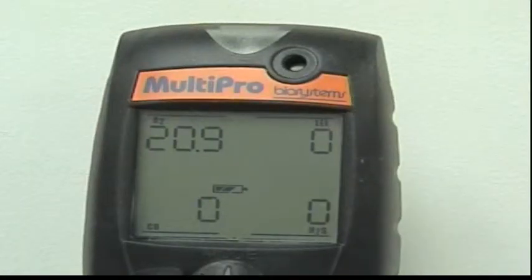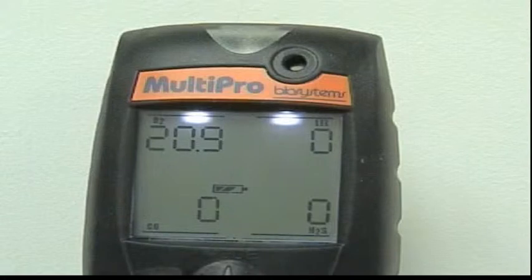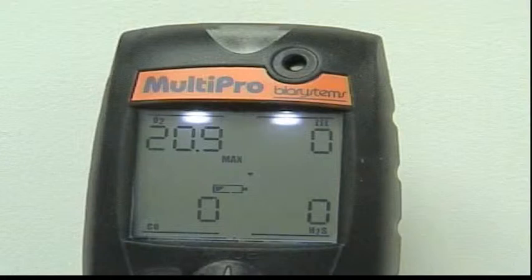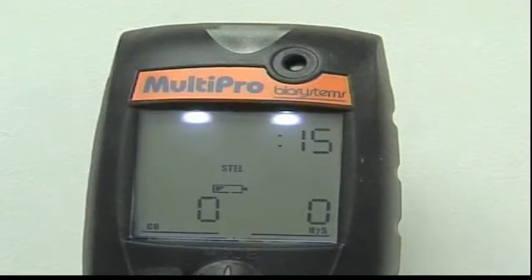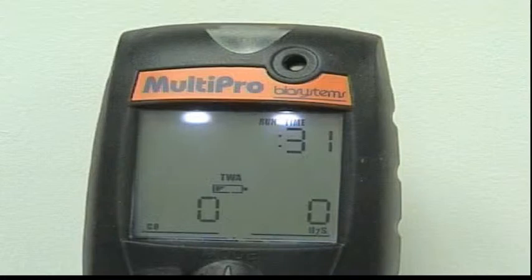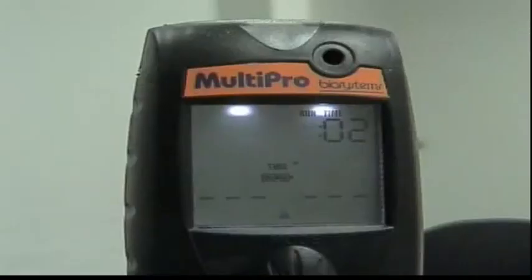To turn on the backlight, just press the mode button once. To view the max readings screen, press the mode button once to turn on the backlight, and then once more. The max readings represents the highest readings registered by the instrument during the current operating session. Pressing the mode button a third time will show the STEL screen, and a fourth time will show the TWA screen. The MultiPro must be in continuous operation for at least 15 minutes before it will be able to calculate TWA values. For the first 15 minutes of any operating session, the screen will show the length of time that the instrument has been operating instead of the TWA values.